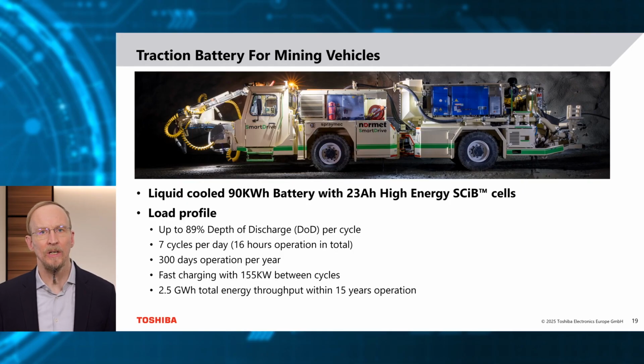Normet is using the 23 Ah SCiB LTO cell in their M-series mining vehicles. A liquid-cooled 90 kWh battery is used as a traction battery. To simulate the lifetime of the battery, the following typical load profile has been assumed. Up to 89% of the battery capacity is used per cycle. There are 7 cycles per day, which amounts to 16 hours of operation in total. There are 300 operational days per year.